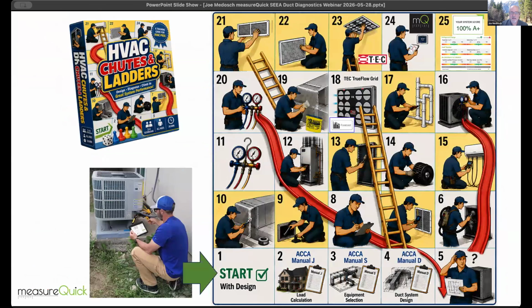So I like that Steve had one of those guides, and I started to be like, oh, I'll let ChatGPT do the chutes and ladders. A lot of the stuff that we'd be doing would start with MeasureQuick. If somebody's out doing MeasureQuick, they do diagnostics and realize that we have an issue, or they want to upgrade to a new system, maybe a heat pump. So you are starting with the Manual J, S. You can probably bypass the D if you jump on the ladder and go up and do the TrueFlow grid and use the forecasting method.